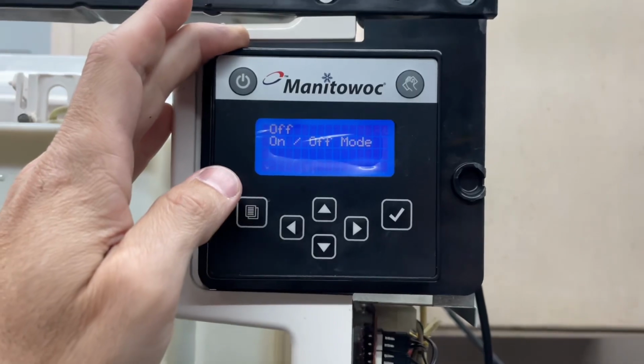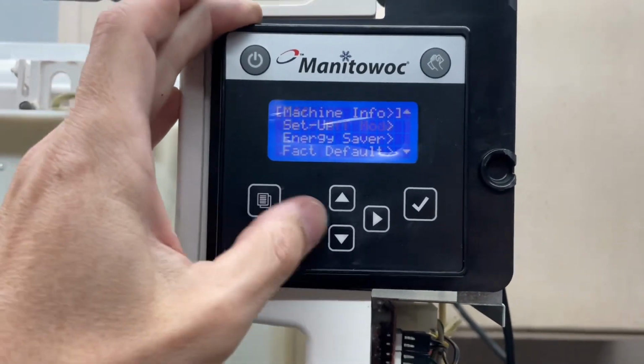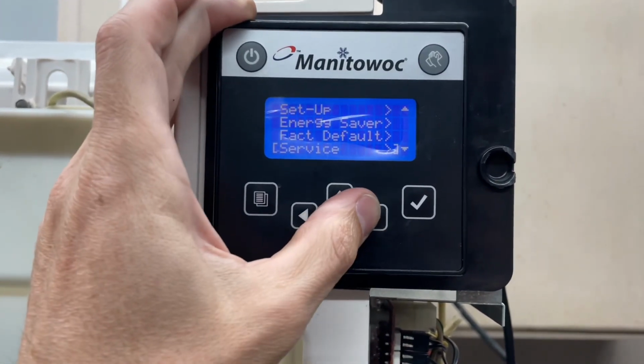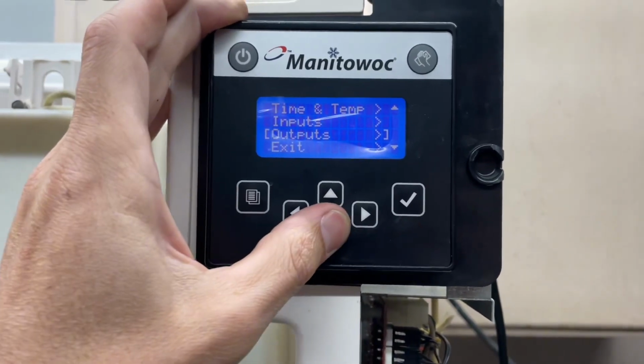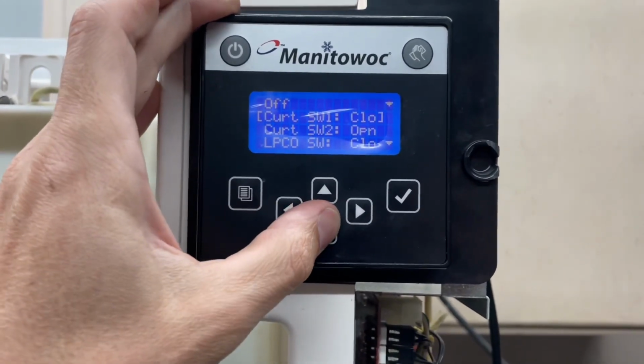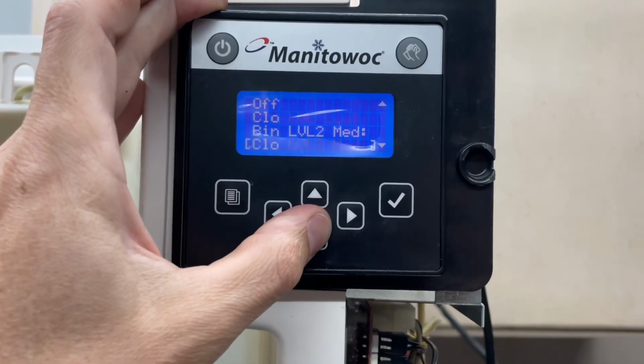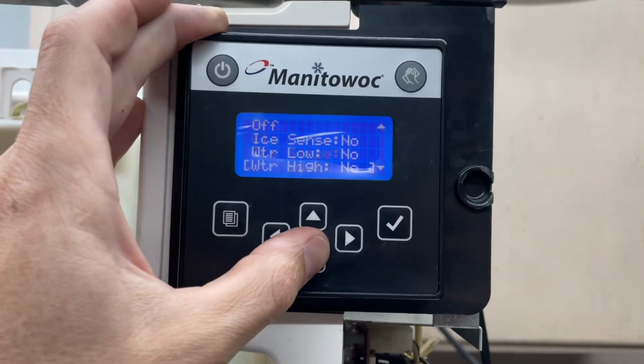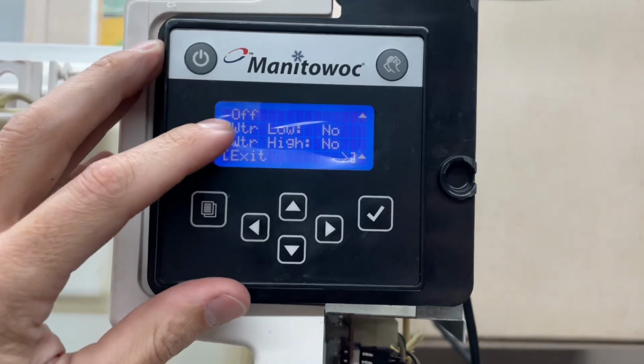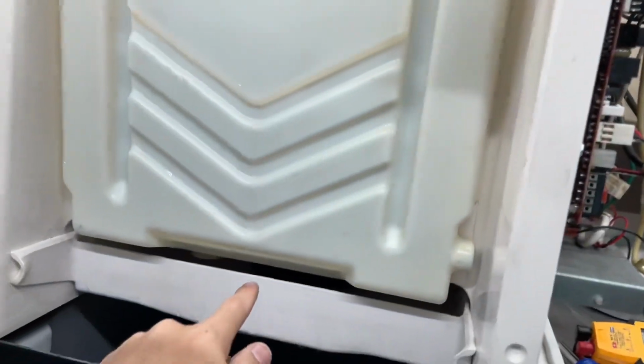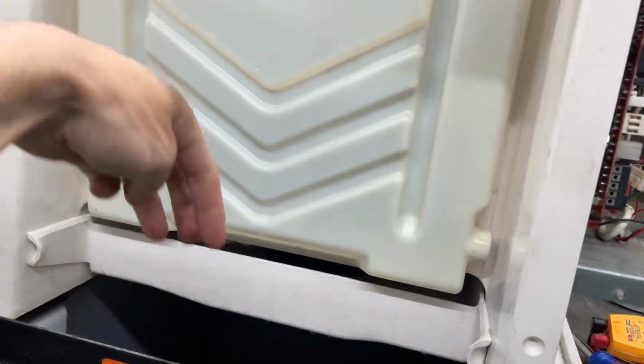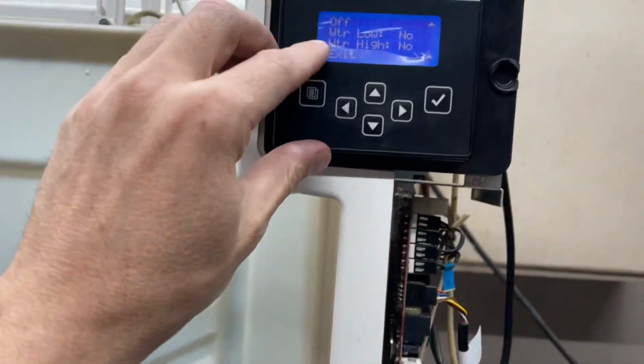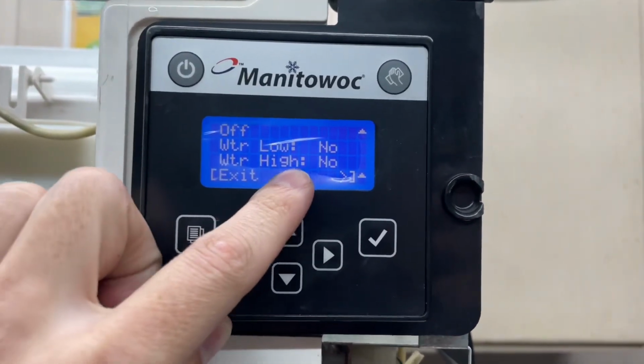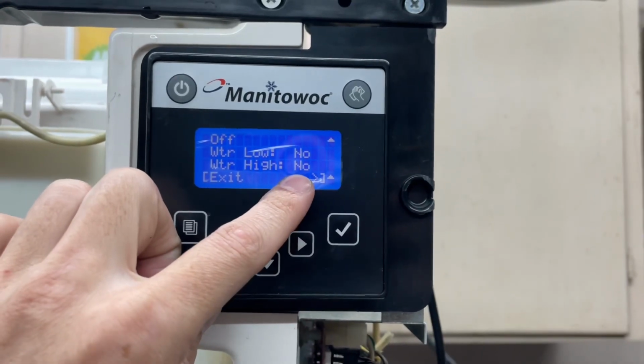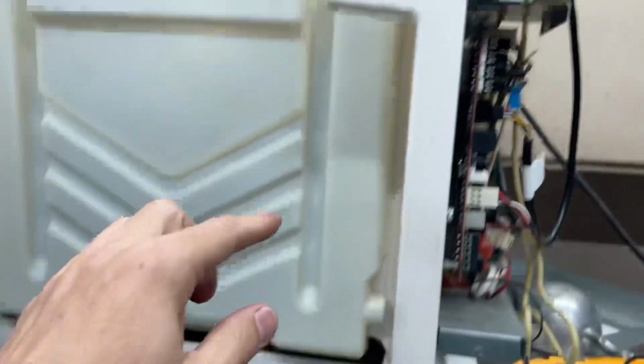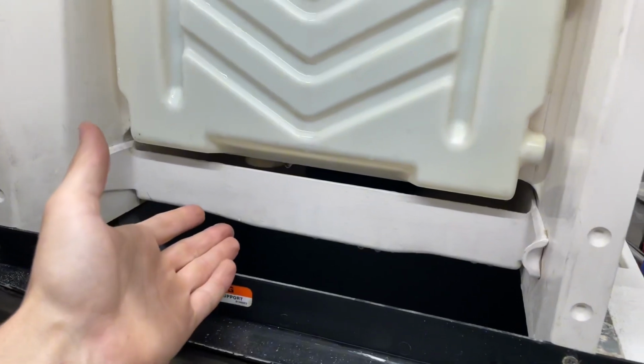to check your water level probe. You're gonna want to go down to service, go to real-time data, go to inputs, and scroll down until you see water low and water high. So water low and water high is essentially your water level probes hanging down into the water, and they will tell you whether or not that probe is sensing water. In this case, they're not sensing water, which is correct. There's no water in the tray.